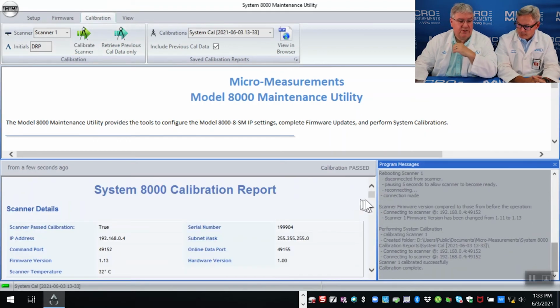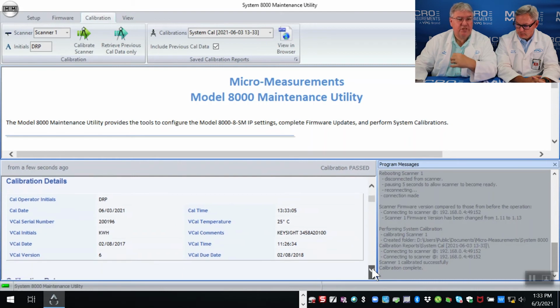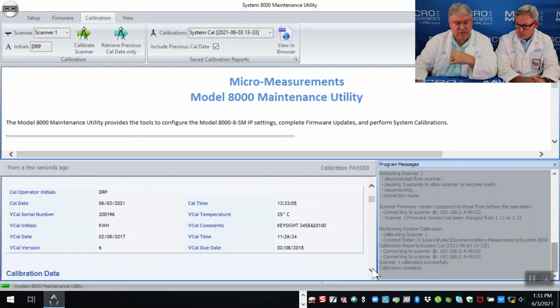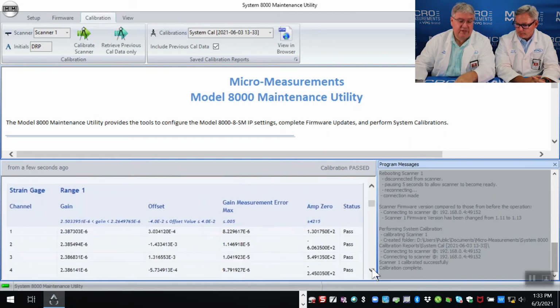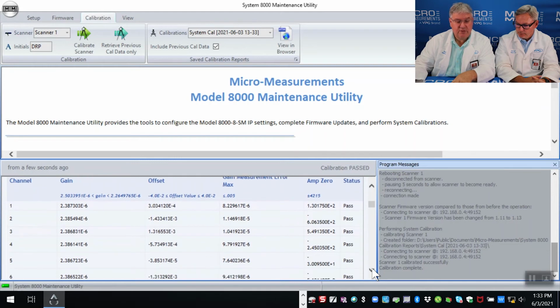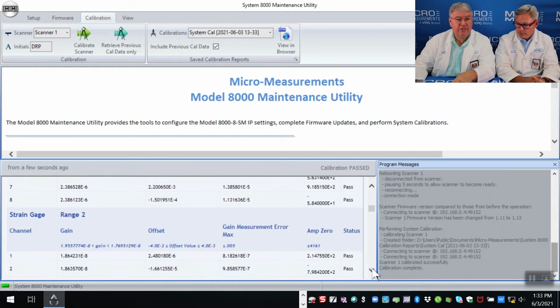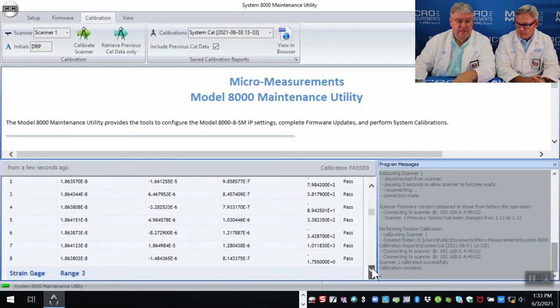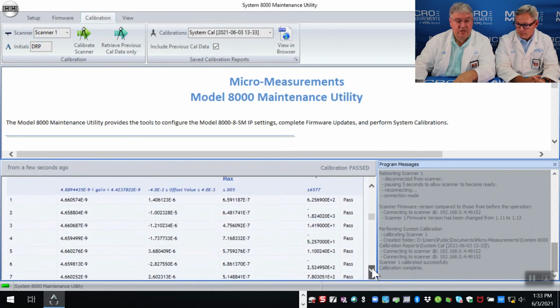And this report is going to be documented on your PC, and so you can actually retrieve previous reports and do a comparison to see what's been done in the past. But as I scroll down the report, you'll see that there's going to be some documentation regarding all the role players. And then for each channel, it's going to have the ultimate result of passing or failing the channels for each of the 5 ranges that it's verifying the integrity of the scanner.